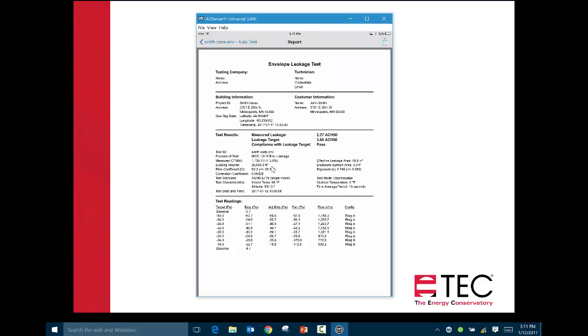In our correlation coefficient, it was pretty windy today, so we ended up at a 0.994. Anything below 0.99, so if we got 0.98 something, we'd probably want to redo that test.